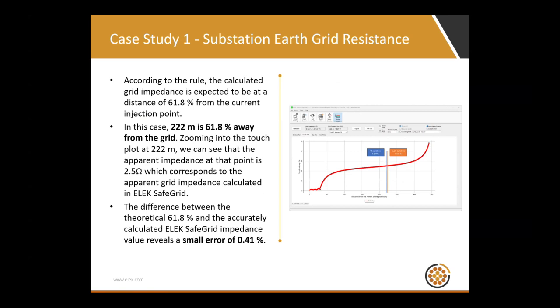And we actually tested the 61.8% rule, and we saw that 61.8% times the separation distance equated to 222 meters from the grid, and that gave us an apparent impedance of 2.5 ohms. Now the software itself can also tell us the grid impedance with more accuracy. And we saw in this case a small difference between that rule of thumb, the 61.8% rule, and the software modeling, 0.41% error.